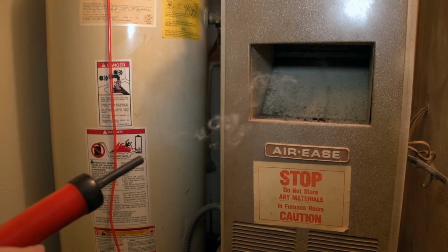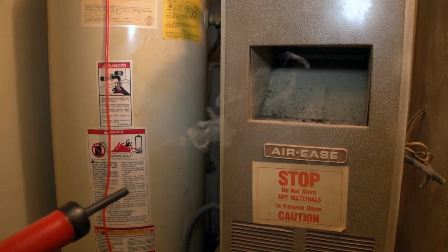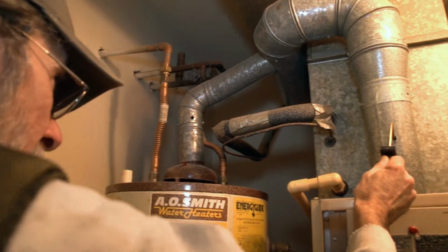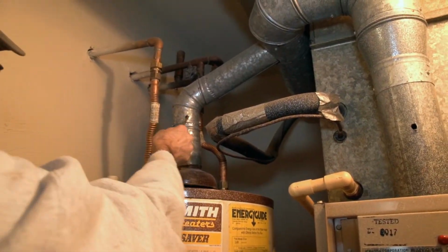The reason for this is that a properly drafting combustion appliance really becomes an exhaust appliance once it's drafting. This is because it's pulling air out of our CAS area much the same as an exhaust fan would. So once we have begun this test, we'll go ahead and turn on one of our appliances, make sure it's drafting properly, and then perform the same CAS test on the other appliance. And we'll do this both with our furnace and our water heater.